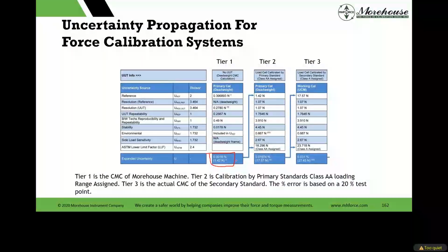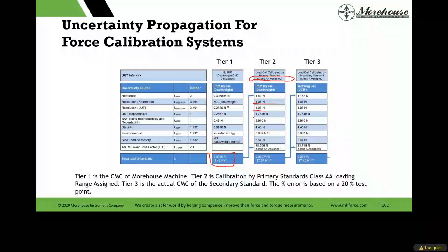So if we're looking at E74, we calibrate a load cell, and then we give that to the customer, those with UCMs or PCMs, you go put that in your machine. We did all these additional tests right here: resolution, converted to Newtons, of course, to stay in the UUT repeatability. Repeatability captured between technicians, captured stability, captured environmental, captured side load sensitivity.